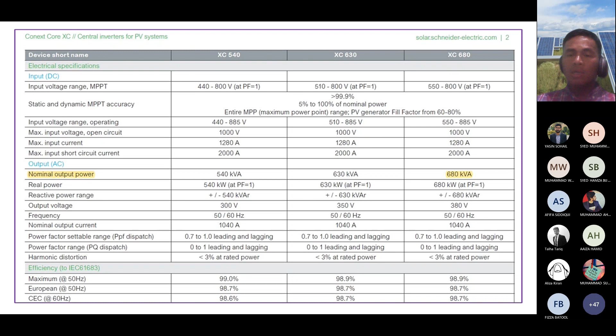This inverter specification affects how many PV modules and what arrangement of PV modules will be connected to this inverter. This is very important for designing this power plant, especially for the PV module installation.